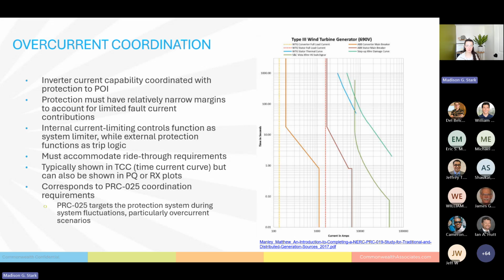So it has both the converter portion as well as the stator portion, which just outputs straight AC power, which is also similarly coordinated. And then this graph actually goes the next step further, where it includes the transformer damage curve, the switchgear damage curve, and then the stator damage curve for the AC portion of the wind turbine. So how I talked about incorporating the flux protection or the thermal limitations of downstream equipment, this is another way that you can show coordination with downstream elements and demonstrate that the system is appropriately protected.